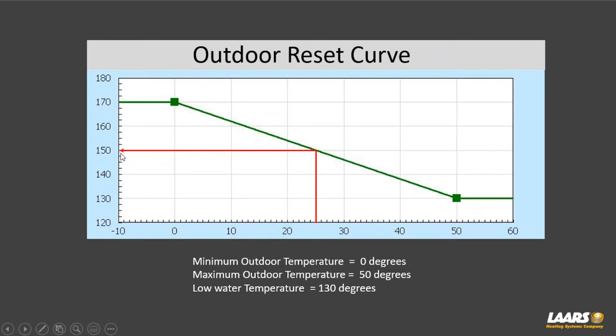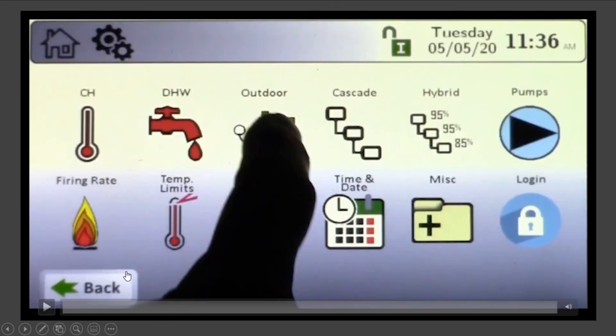Keep in mind that's your supply temperature. Your return temperature back to the boiler, if designed around a 20-degree delta T, would be 130. At a 30-degree delta T, you'd be returning at 120. This is important for condensing reasons in condensing applications.